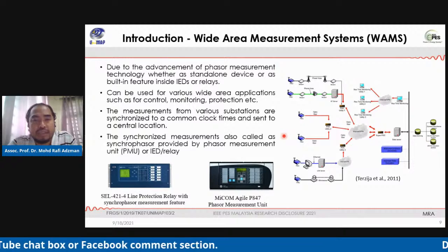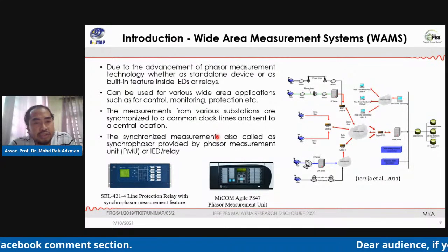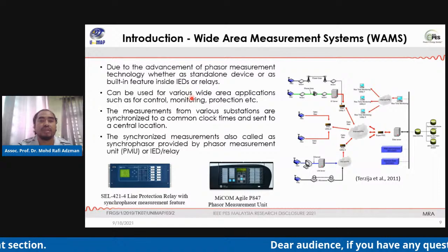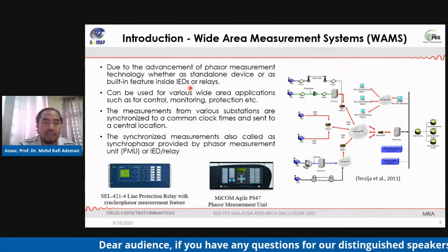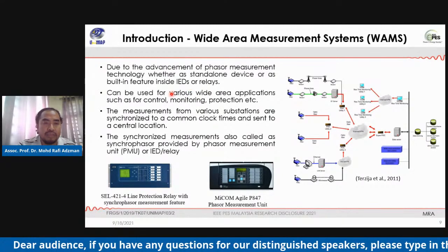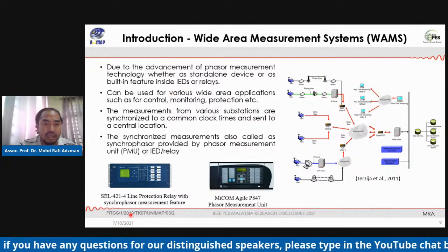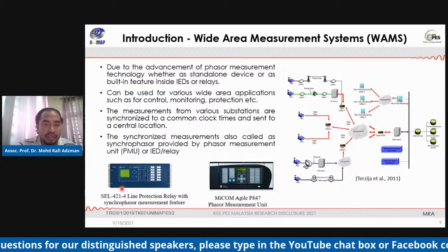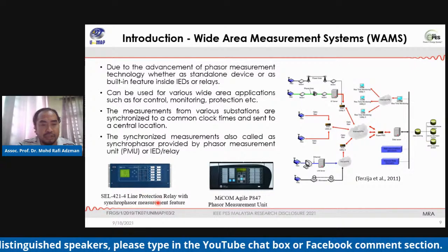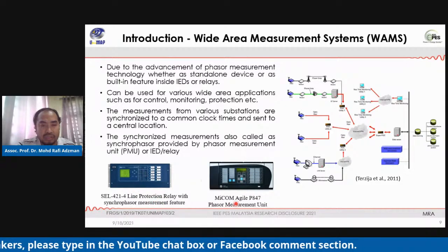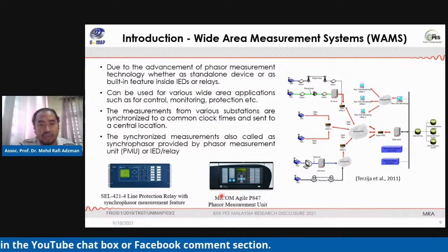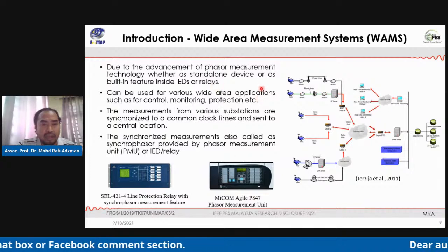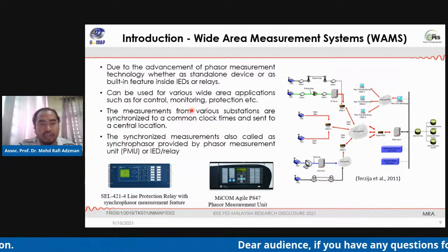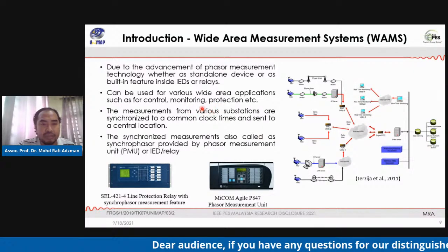The wide area measurement system, or WAMS, was introduced due to the advancement of phasor measurement technology, whether as a standalone device or as a built-in feature inside the IEDs or relays like this one. In this example, the line protection relay has synchrophasor measurement inside it, and this is the standalone device, the PMU. This application is normally used for control, monitoring, and protection.